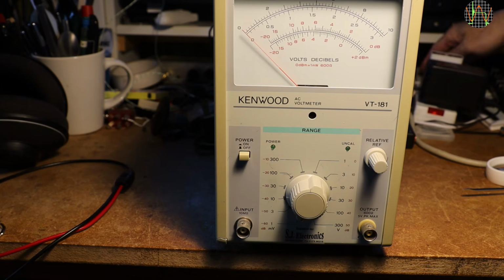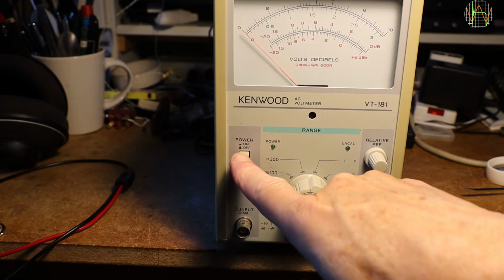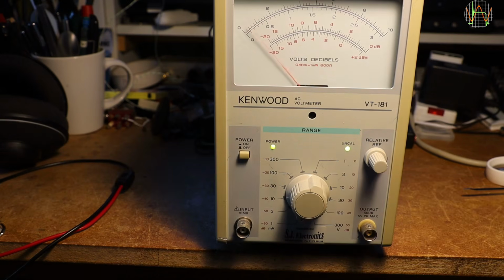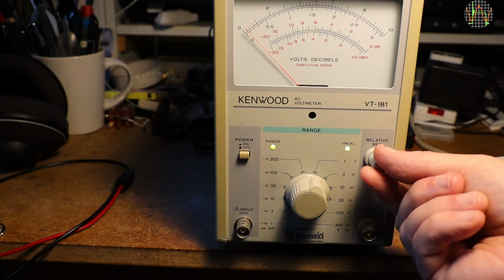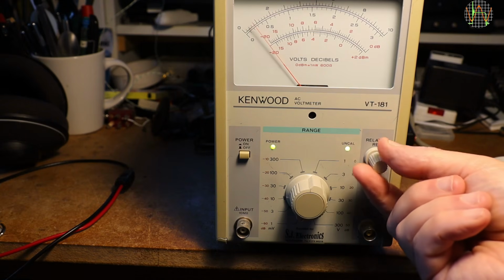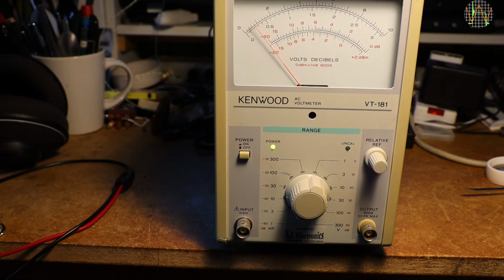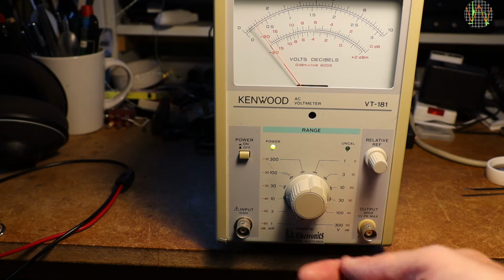With that done, it's time to power on, although, as I already explained, the transformer is already powered on as soon as you connect the unit to mains. The needle is not quite on zero and the uncalibrated light is on too. The uncalibrated status is because the relative pot was not in the off position. This knob allows you to adjust the needle to a particular value, but of course it means the scale markings are no longer applicable, hence uncalibrated.